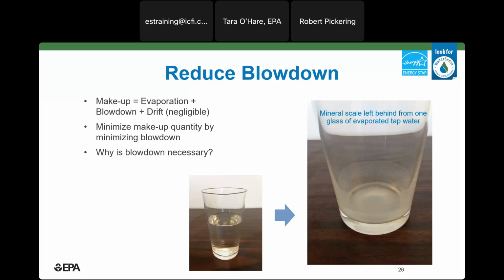So if you recall our schematic from the cooling tower, the only water that's being added to the system is from makeup water. When operating properly, the only significant ways water is leaving the system is through evaporation and blowdown. The drift should really be negligible. So reducing the cooling tower blowdown, as I mentioned, is the biggest opportunity for savings.